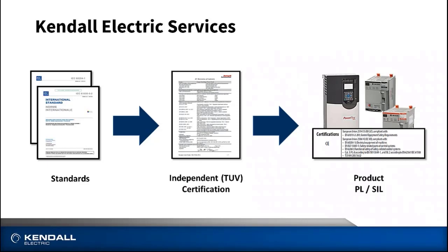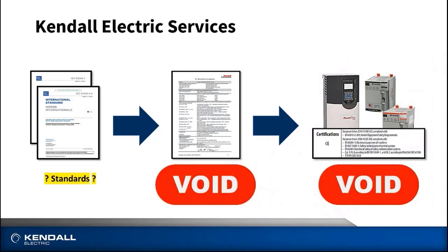Sending these products in for repair can absolutely create a problem. Thus, the belief that new product purchase is the only solution for replacement. Alter or change a safety product's components, chips, boards, or overall product assembly, and you knowingly change its performance. With a change in performance, the safety integrity level and performance level ratings then become unknown, and the capability of the overall safety system is compromised.